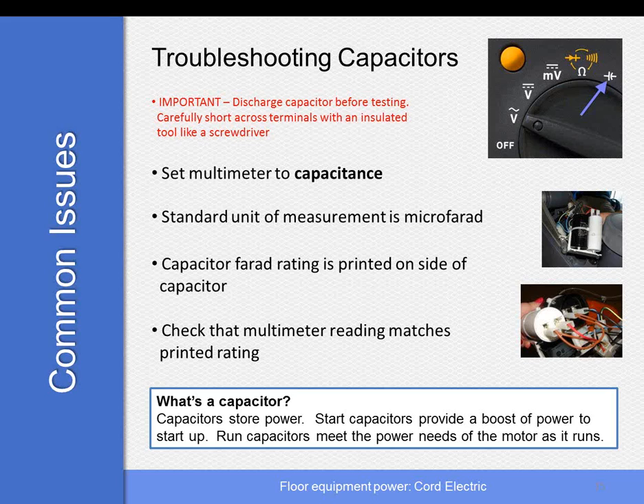The unit of measurement in most capacitors on these machines is going to be a microfarad. The standard is a farad. It'll be an F, capital F. The rating will be printed on the side of the capacitor, and normally it could be within a percentage, 10%, give or take, up or down. As long as your capacitor is within this, it'll be good. If it's out of spec, you'll need to replace it.